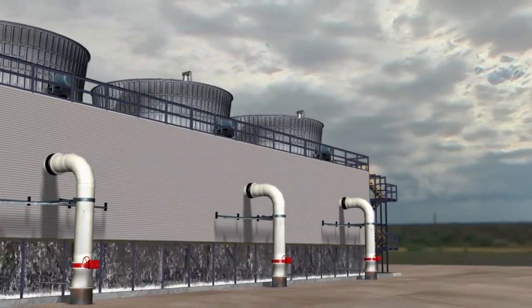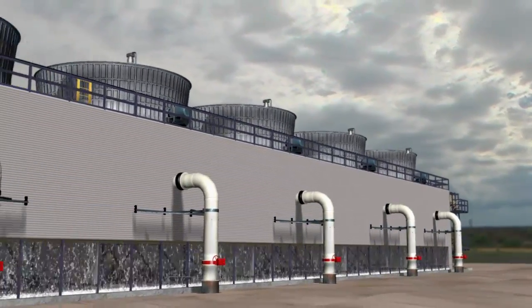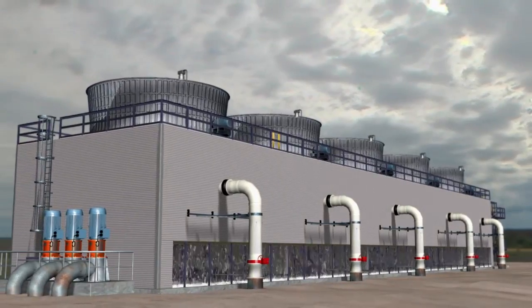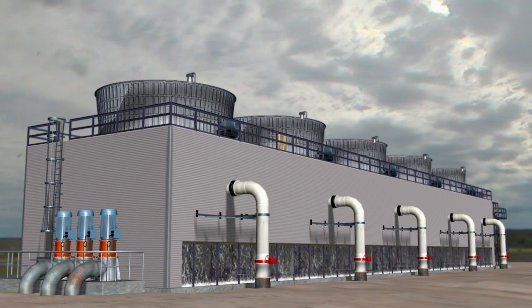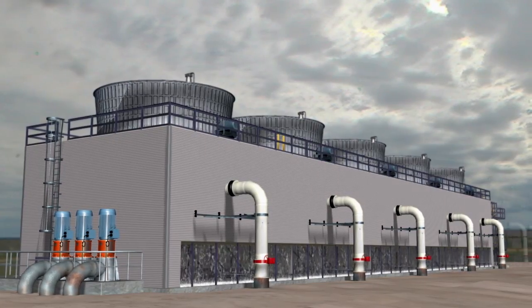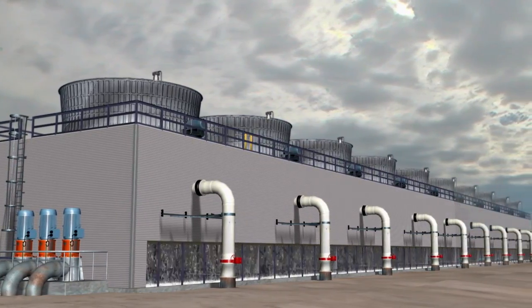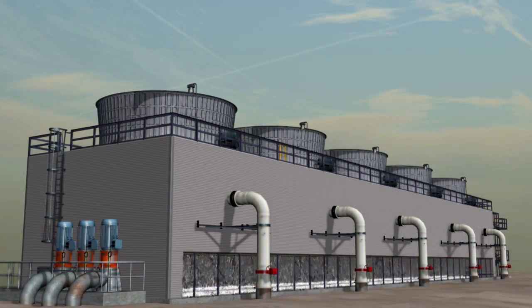The design of counterflow cooling towers has been flawed since its inception. Water pumps are not in sync with the number of cells. For example, you might only see 3 pumps for a 5 or 10 cell cooling tower. Engineers design cooling towers to perform in the hottest part of the year.